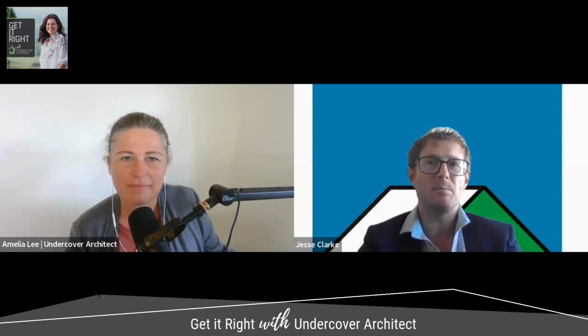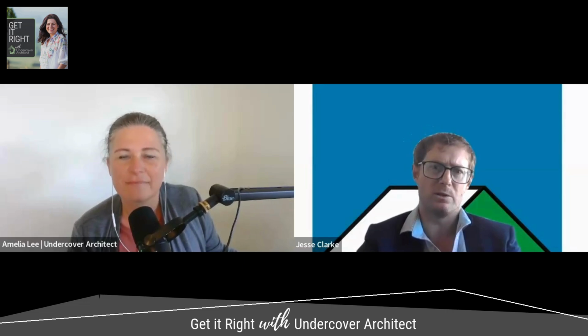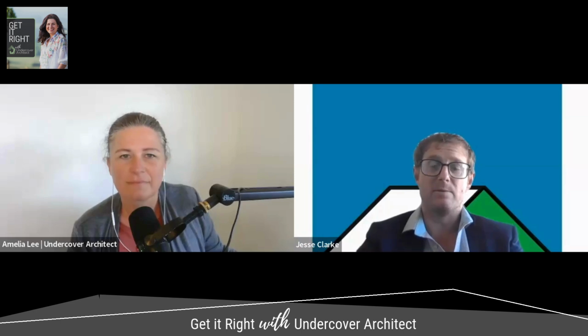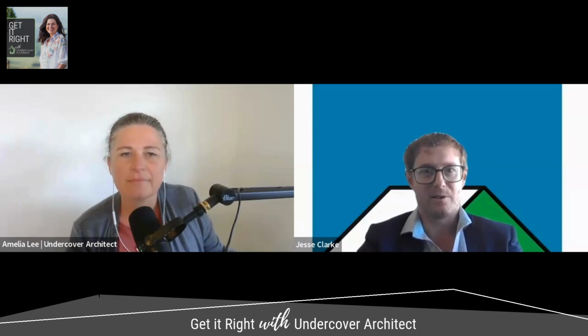It's like, condensation's harmless. It's just water. It's that prolonged time factor in there when it's constantly wet, materials are constantly damp. They may not be condensation. It may just be damp building materials, because when building materials get cold, they start to absorb more moisture into the pores. So you've got these damp building materials creating higher humidity surrounding that building material. When you get higher humidity above 70, 80% for prolonged period of time, then you potentially induce mold growth. And that's a potential problem that happens even when you don't have liquid condensate occurring.